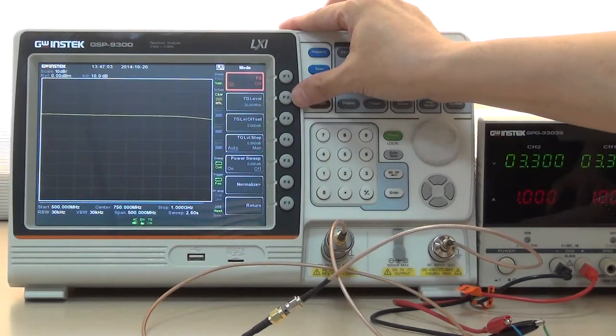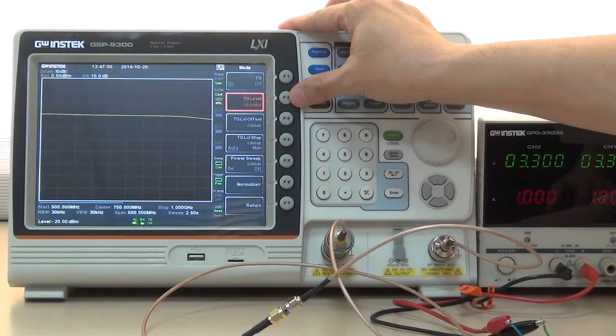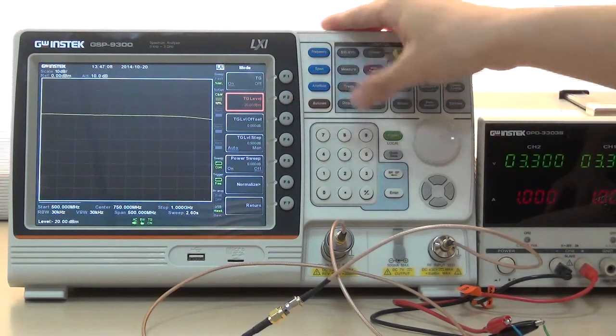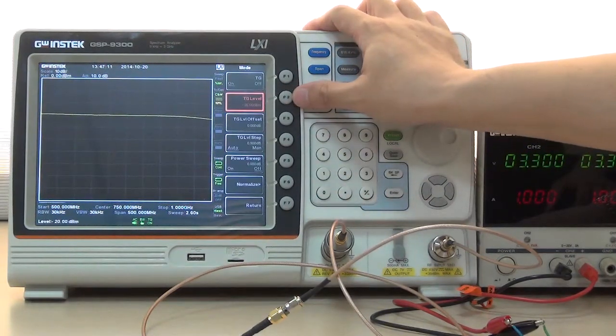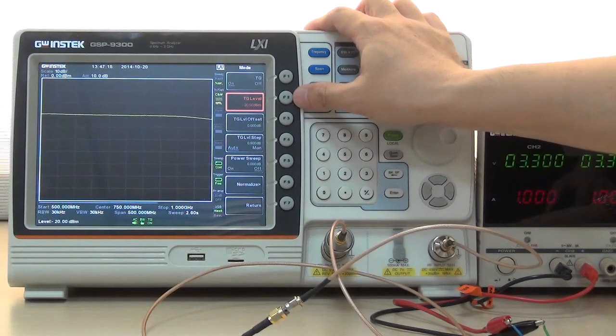Next, press F2 Tracking Generator level and input minus 20 dBm to set Output Power as minus 20 dBm.